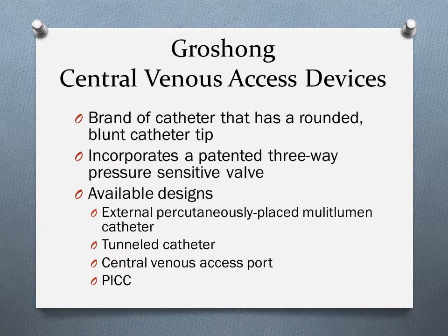The Groshong central venous access device is a brand of catheter. It incorporates a patented 3-way pressure-sensitive valve. You have negative pressure, the aspiration, which opens the valve inward for blood sampling. Positive pressure by the infusion will cause the valve to open outward, and with neutral pressure the valve remains closed.